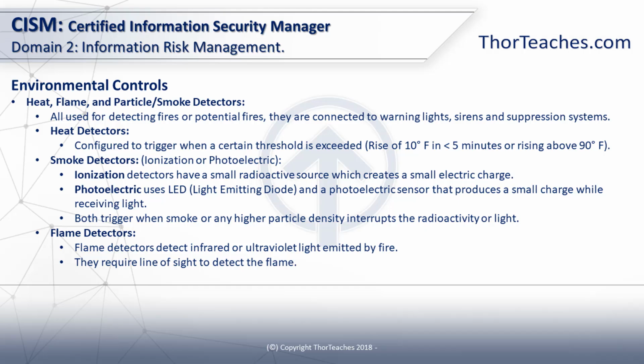We talked about the smoke sensors earlier. Those were the ones where, when the particle density rose too high, they would trigger. They can either be ionization detectors, which have a small radioactive source that creates a small electric charge, or a photoelectric sensor that uses an LED, that also produces a small charge while receiving light. They both trigger when smoke or high particle density interrupts the light or the radioactivity.